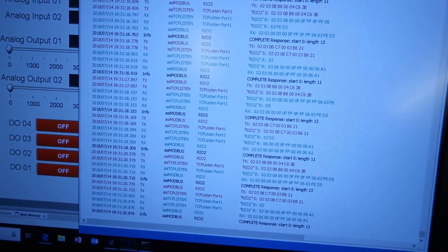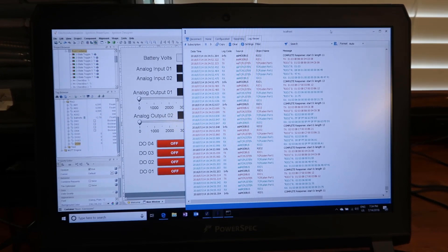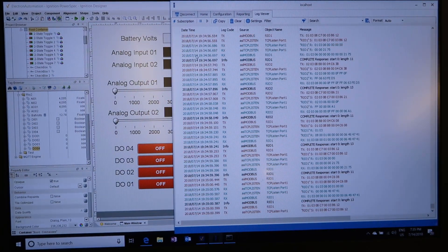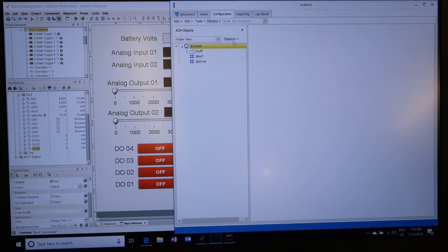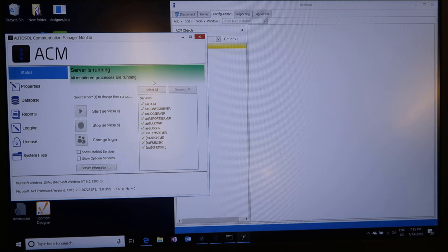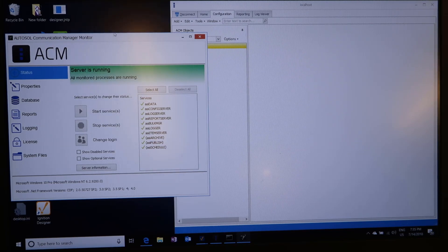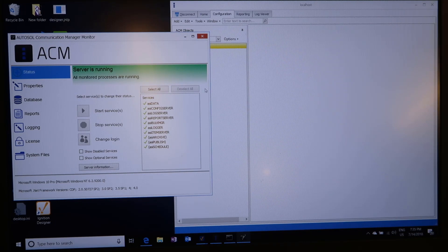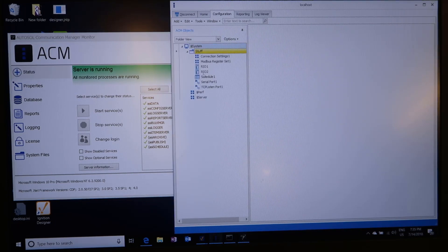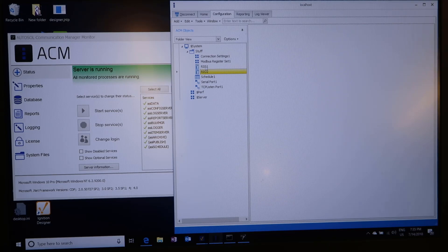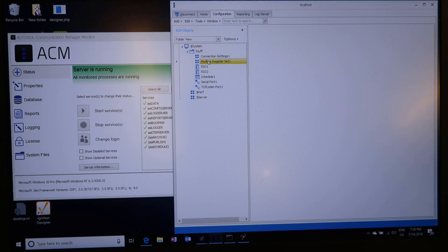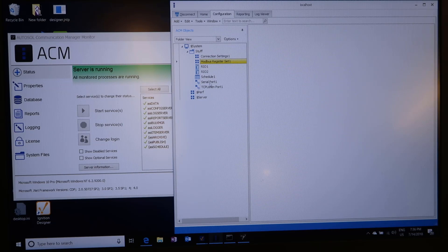Now we just need to hook everything back up here. We actually go over and look at my polling engine. It was failing. It couldn't connect to the device. And then, bam, it's communicating happily now. But let's go ahead and I'll give you a quick crash course. I apologize. I'm not going to do this. I'm just going to use my camera here. So, a couple things. This thing right here is called ACM. It's AutoSol Communication Manager. So ACM is an OPC server. And what you do is you fire the thing up. And you start adding devices. So in here you add objects. These are objects connect to Modbus devices. In this case, we had two. And these objects use a register set, a Modbus register set, to tell it how this particular Modbus device has customized Modbus. Modbus can be customized, unfortunately.